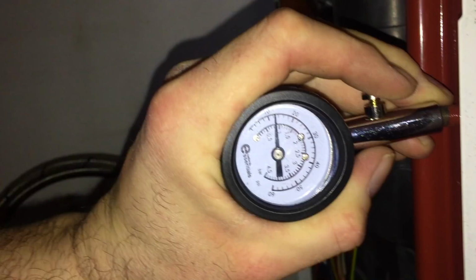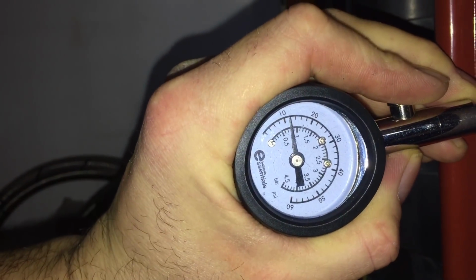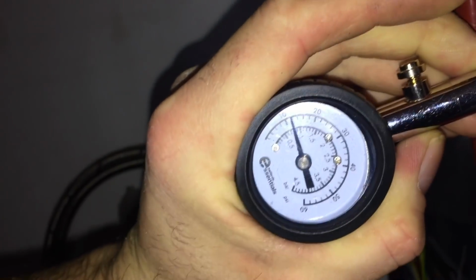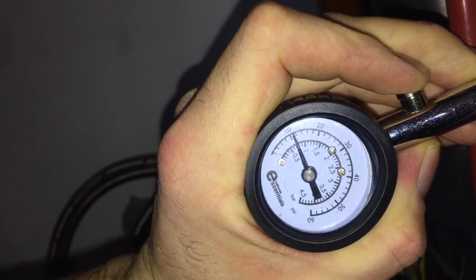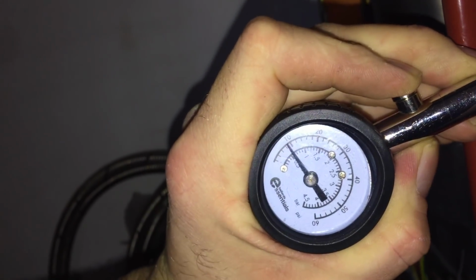Right, so this nut here is just the end of the filling loop. I undo that when I'm draining because I think this is why it's over pressurizing. So I just leave that hose dangling and just keep an eye on, see if that's dripping. That way I know the other end of the valve's letting by. While it's drained, I obviously pump up the vessel because that's gone flat because it's been over pressurized the whole time. So I overfilled it a little bit. Now I'm just letting some of the excess air out.